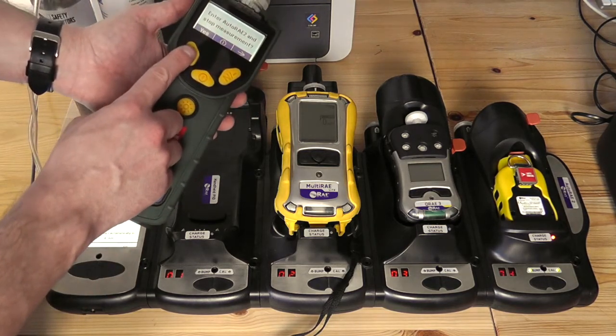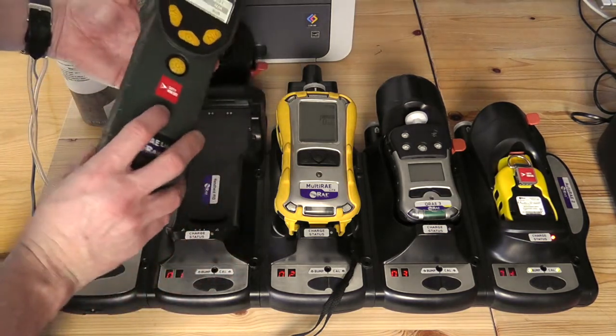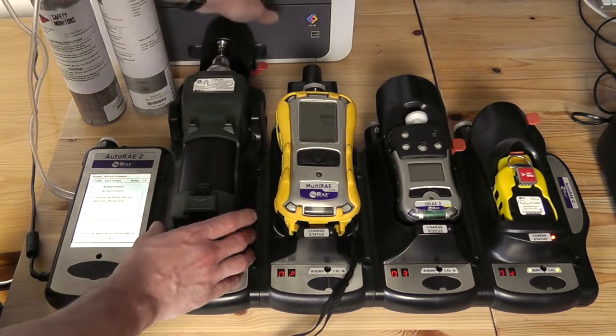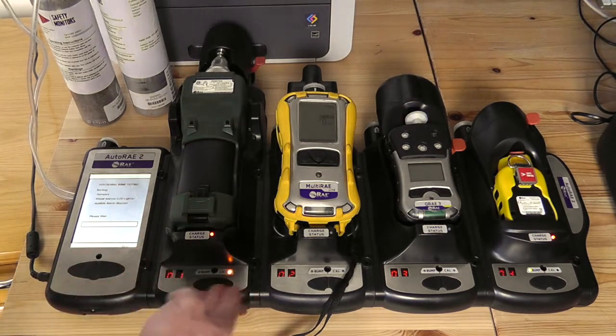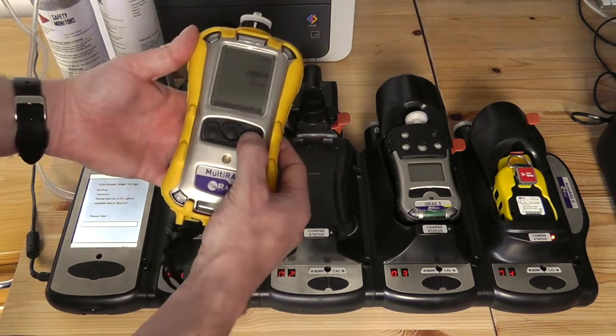Not just in standard communications mode — hit yes, and it's now ready to communicate with the AutoRAE2. Apply the device, and this will now wake up the device and wake up the communications. The exact same procedure applies on the MultiRAE.